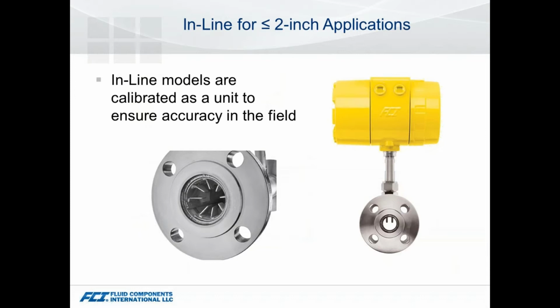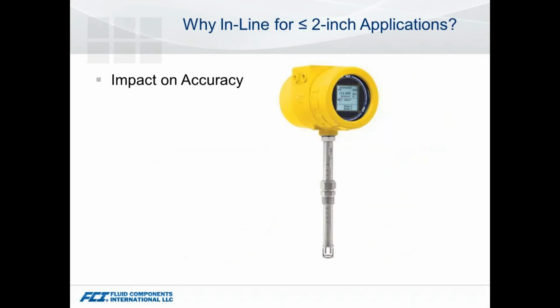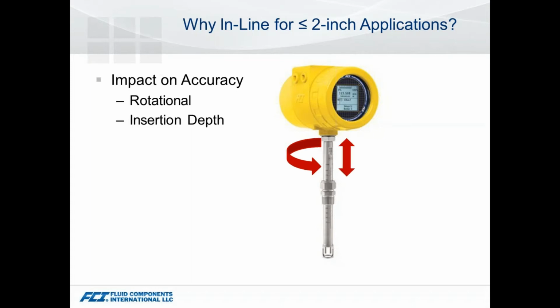As far as the inline models go, we look at going to this style for a few reasons. One of them primarily is that by calibrating the device in that spool piece, it really ensures overall accuracy in the field. The reasons for this impact on accuracy, the first thing you have is rotational effect. So for smaller line sizes, if I have more rotational effect, it's going to introduce a little bit larger error than it would on the larger line sizes. The next one we deal with is the insertion depth. So if I'm off a little bit on the insertion compared to where it was positioned at the factory in calibration, again, introducing larger errors. And then you have some sensor blockage. The sensor itself in a small line size creates blockage, which creates a less than ideal flow pattern, also creates some additional pressure loss that none of us want to deal with.